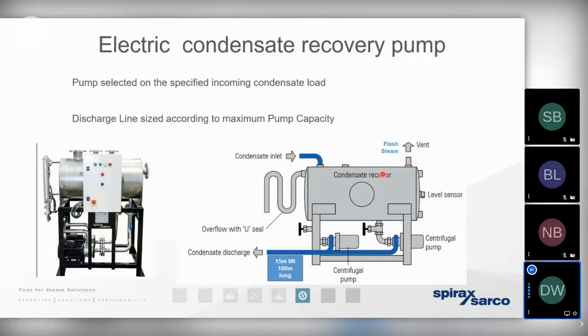So it's important that we also size the flash steam vent correctly because we need to vent that energy to atmosphere, partly to allow that energy to be dissipated so we're not causing cavitation of the pumps. But another key benefit is once that flash steam's been vented away, the condensate will now exist as a single phase liquid. So we could now pump that condensate back to the energy center in a much, much smaller pipe diameter because we're pumping a liquid here.